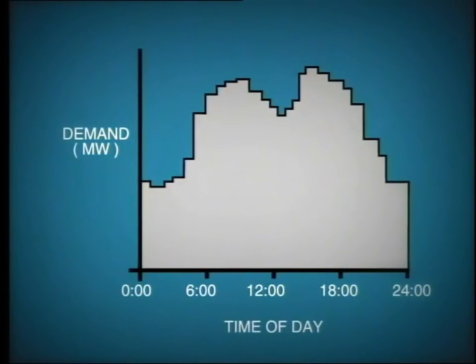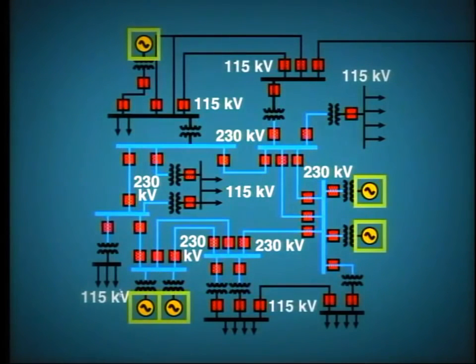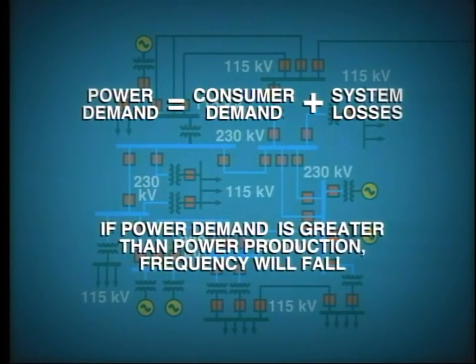The demand for megawatts varies throughout the day as consumers switch their electrical devices on or off. As we cannot store electrical energy, at least in large quantities, the combined power output of all generators connected to the system must exactly equal the total power demand at every instant of the day. The total power demand consists of the consumer's demand plus power system losses, which may be as high as 4 or 5 percent. If at any time the power demand is greater than power production, then the frequency will fall.